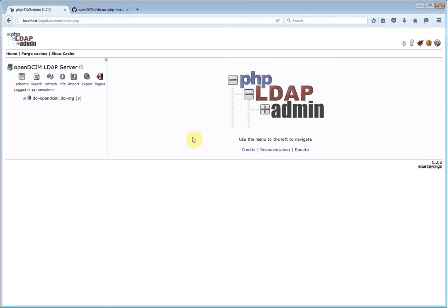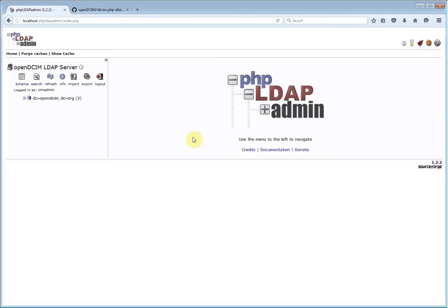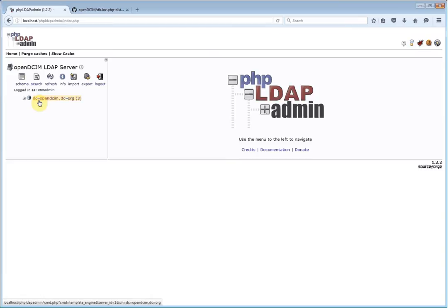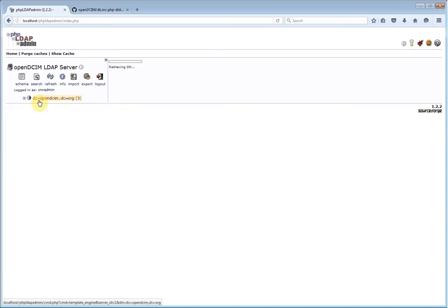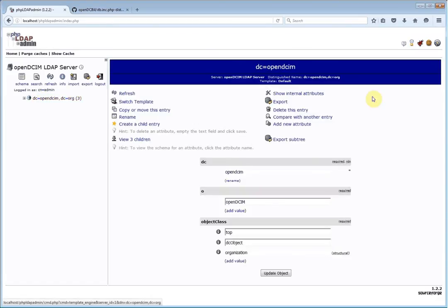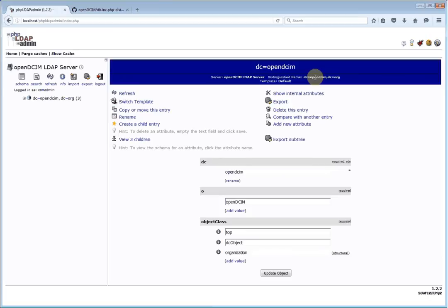I've got a site that's already set up with OpenLDAP, so let's just go ahead and take a look at what I did for the LDAP. I'm using OpenLDAP here. You can always use pretty much any LDAP compliant LDAP server, so you can even use Active Directory if you've got that set up at your business location. I have created an organization with the distinguished name of DC equals OpenDCIM comma DC equals org. Typically this is just whatever your URL or your domain name for the LDAP server is, and each stanza that's in between the periods is a DC section you put it in the right order.